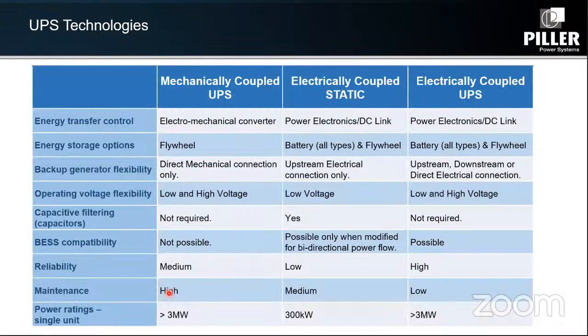Let's look at an overview of the three technologies available. On the left is the mechanically coupled type I explained previously. In the center is the electrically coupled static type, which is very commonly used. On the right is what we call electrically coupled UPS, from Piller. The energy transfer control is through power electronics and a DC link, which is why we fall in the electrically coupled category. The advantages are low maintenance, longer lifetime, and fewer discrete components.